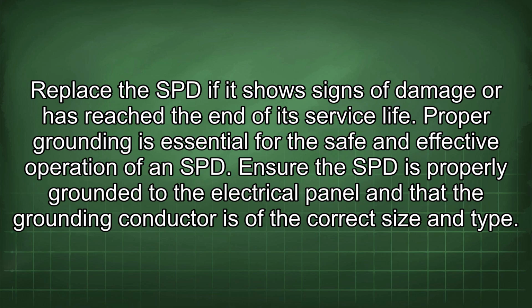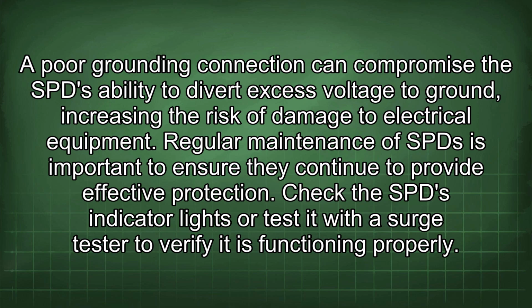Proper grounding is essential for the safe and effective operation of an SPD. Ensure the SPD is properly grounded to the electrical panel and that the grounding conductor is of the correct size and type. A poor grounding connection can compromise the SPD's ability to divert excess voltage to ground, increasing the risk of damage to electrical equipment.